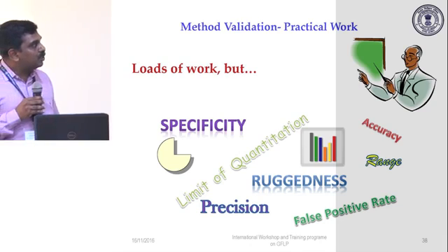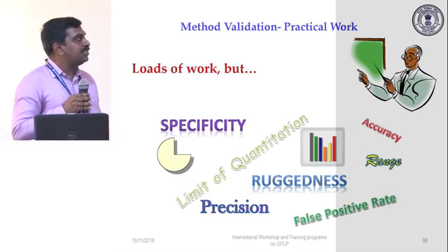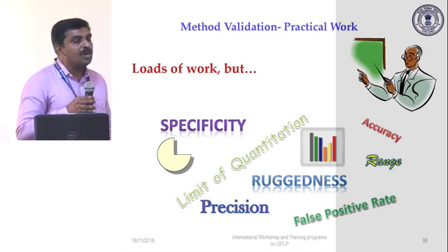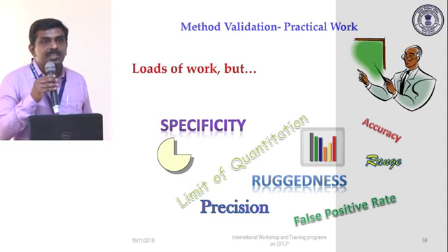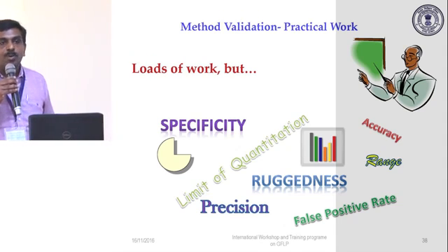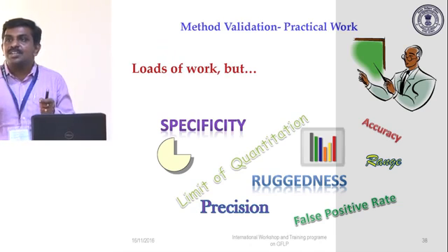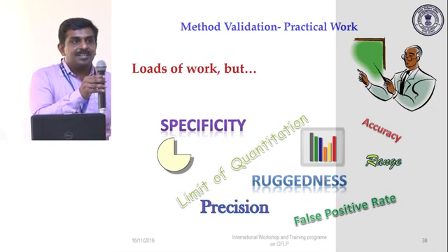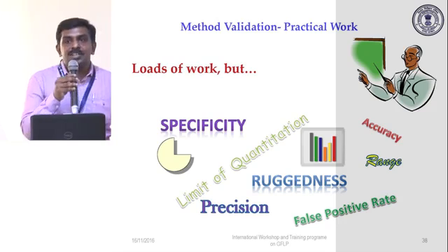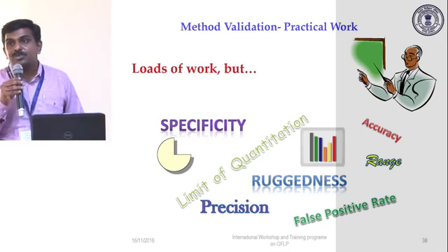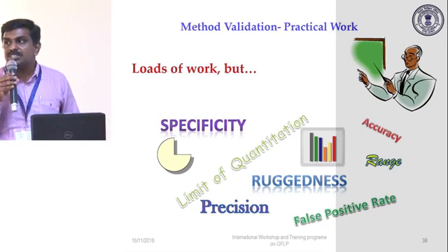The person who is doing validation should have knowledge about the technology as well as the need of the lab. The requirement of your customer or the need of the lab is from this range to this range. He has validated from another range to another range. That validation is of no use. That is what I was telling about the preparation for validation.